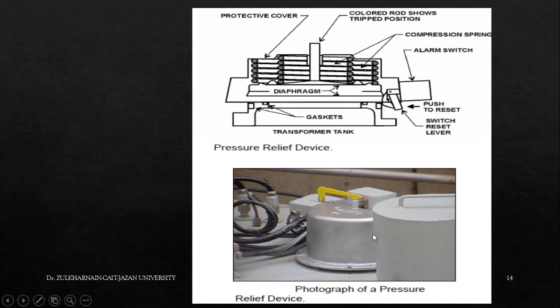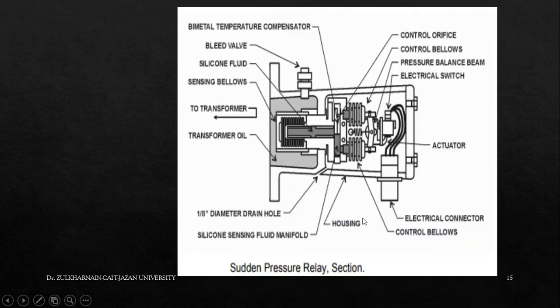So this is another pressure relief device which is used in big transformers. You have the alarm switch here, and you have different levers, gaskets, diaphragms, and protective layers which are used for working of that. And you also have a relief device, just like a pressure cooker. You also have this sort of thing in a transformer. This is the sudden pressure relay section. Here we have different devices, control orifice, electrical switch, and different transformer connections, and the temperature compensator. So temperature can be checked and maintained.